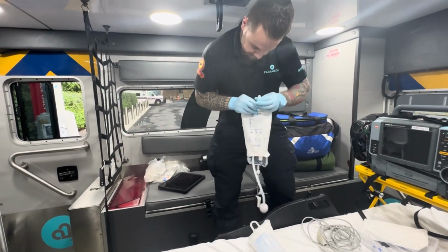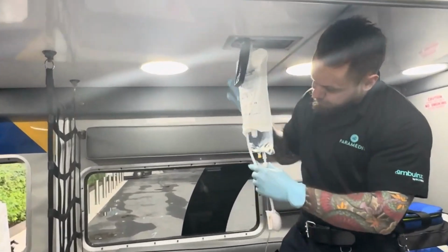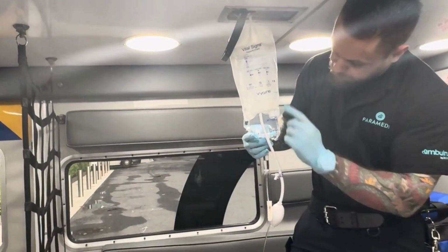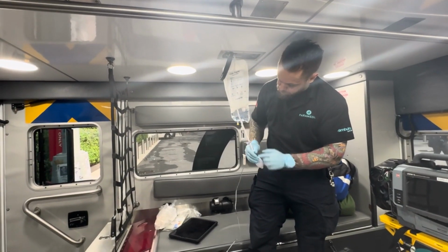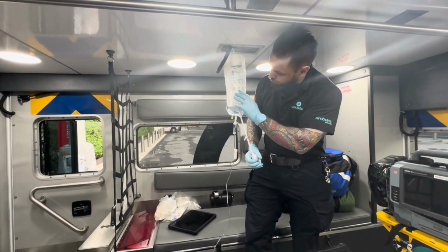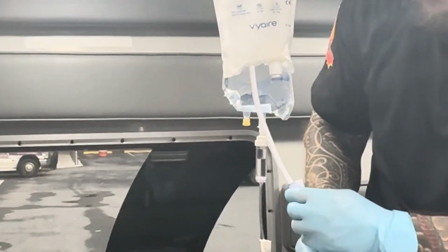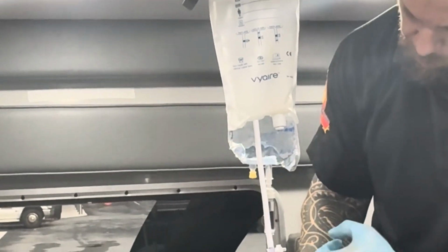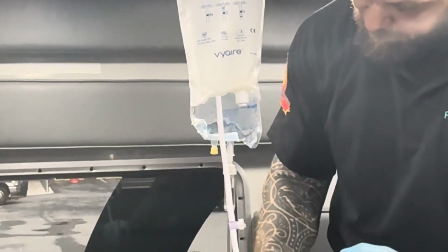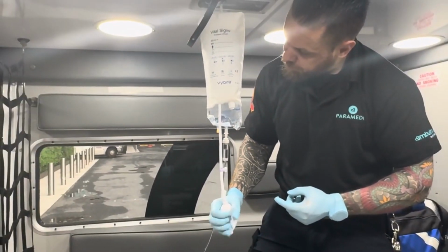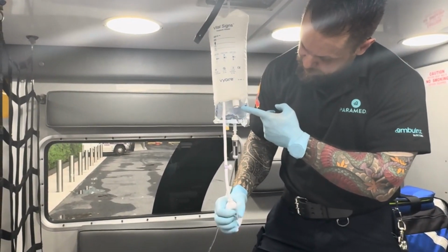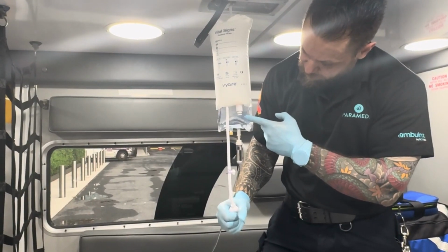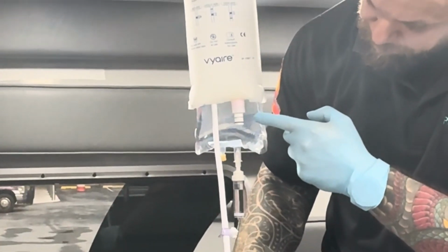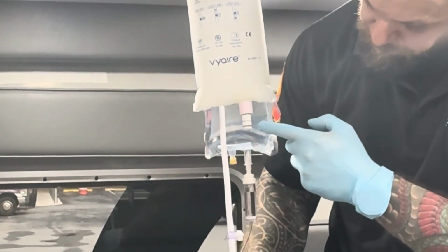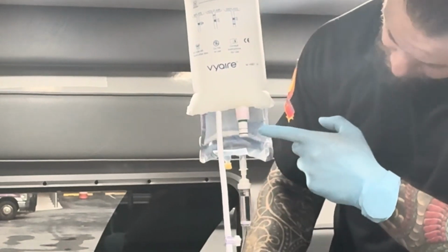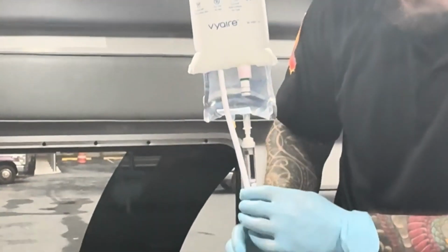Yeah. So now I'm going to hang this up. So once I hang this up, you see how the bag protrudes because this is not made for the 500. What I'm going to do is I want to pump this up until it says 300. So I'm going to look at this dial until it's correctly pressurized, 300 millimeters of mercury. So we're going to inflate with this off portion to this side, so the air is coming into the cuff. So I'm looking at this gauge right here. As it pressurizes, I'm looking for the green. Green means it's 300. So 150. All right, green comes out, 300. I see 300. And then you're gonna close this off so no air is escaping.